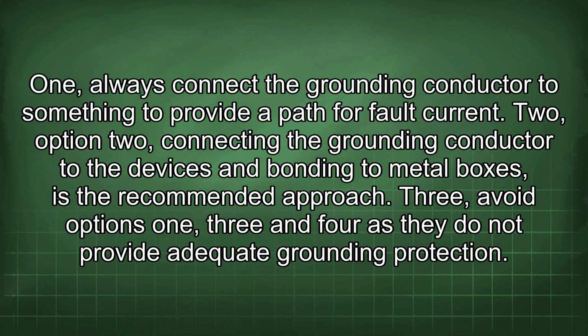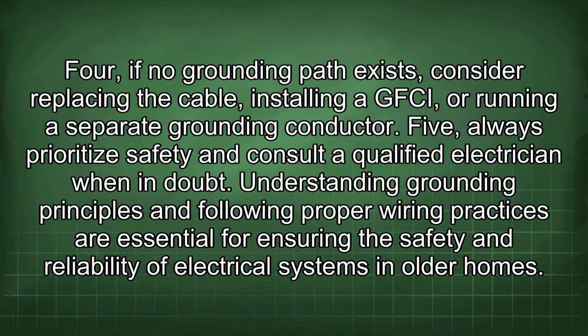1. Always connect the grounding conductor to something to provide a path for fault current. 2. Option 2, connecting the grounding conductor to the devices and bonding to metal boxes, is the recommended approach. 3. Avoid options 1, 3 and 4 as they do not provide adequate grounding protection. 4. If no grounding path exists, consider replacing the cable, installing a GFCI, or running a separate grounding conductor. 5. Always prioritize safety and consult a qualified electrician when in doubt.